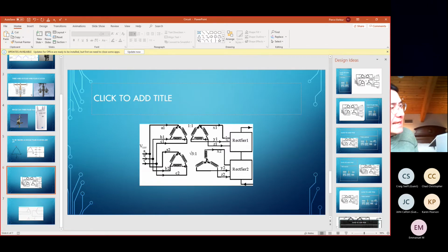transformer, you cannot connect X1 and X2, even though they're in essence the same phase, because these transformers have shifted them such that the voltages are not in sync. And therefore there will be a voltage potential at all points except 2 on the relative sine waves. So you dare not connect these three-phase supplies together, but once you rectify them through the 2 separate rectifiers, everything is DC and it can be connected on the output. Now, this particular diagram is not accurate for the type of 12 pulse that we use at Yaskawa, because it shows rectifiers in series and we use rectifiers in parallel, but that's a small detail that we'll pick up during the harmonics class.